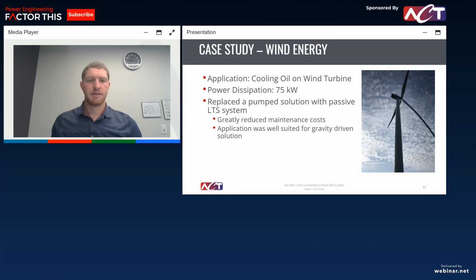Next, I'm going to look at a few case studies. I won't spend a ton of time on these so we can get to some Q&A. First, a solution we did for a wind turbine. On this wind turbine, they had a pump loop that was cooling gear oil. The big gears in your wind turbine, due to friction, get very hot. They had to cool that oil down and cycle it back to the gears. We designed a loop thermosyphon for them that dissipated 75 kilowatts, and it replaced that past pump system.